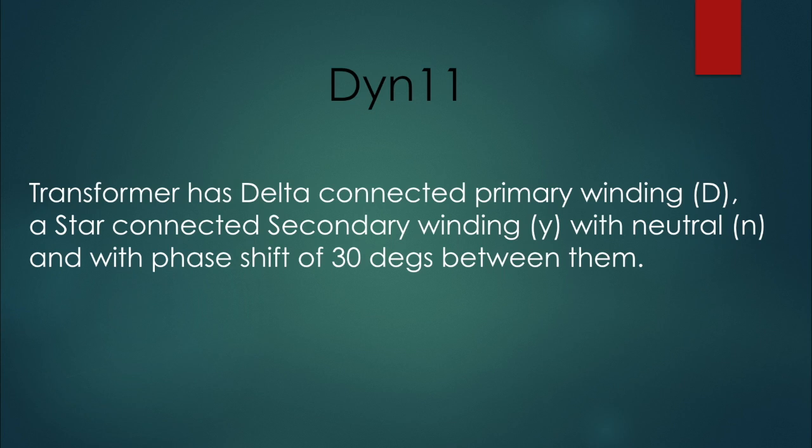This vector group is important while connecting two transformers in parallel. If you connect two transformers with different vector groups in parallel it may result into a short circuit or there will be some disturbances in the system.